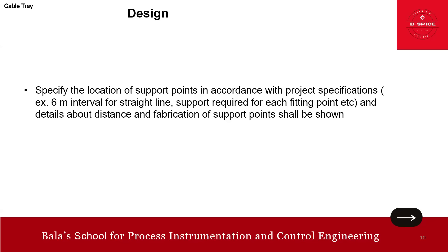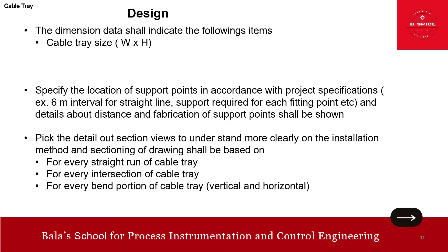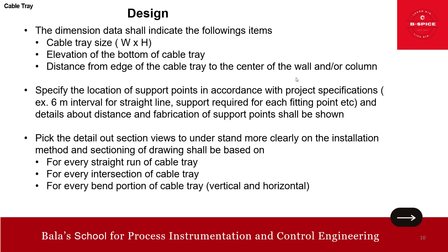For dimensional data: specify the cable tray size - width and height - the elevation of the bottom of the cable tray, and the distance from the edge of the cable tray to the center of the column or wall. Specify the location of support points per project specification - for example, 6-meter intervals for straight runs. Include section views at every straight line, every intersection, and every bend portion of the cable tray, both vertical and horizontal.